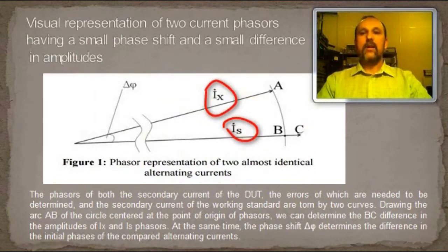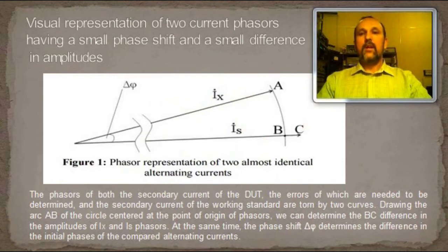When calibrating current transformer, two alternating secondary currents are compared, different in the initial phase in units or tens of angular minutes. The difference between the amplitude values of the compared currents is often thousandths, hundredths and or tenths of a percent for the calibrating current transformers used in power engineering. This often convenient to represent alternating current as a phasor to solve electrical engineering tasks.